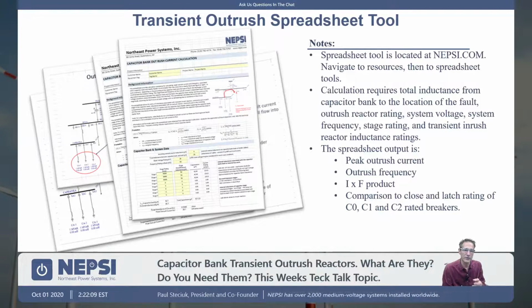You take those values and compare them to the feeder breakers within the substation. You want to make sure that you don't exceed the rating of the breaker. So this is part of your design process: what type of feeder breakers am I using? What is the possible outrush current and outrush frequency? What is the IF factor? You compare the calculated value against those ratings. If you exceed the ratings, then you need to add some inductance.